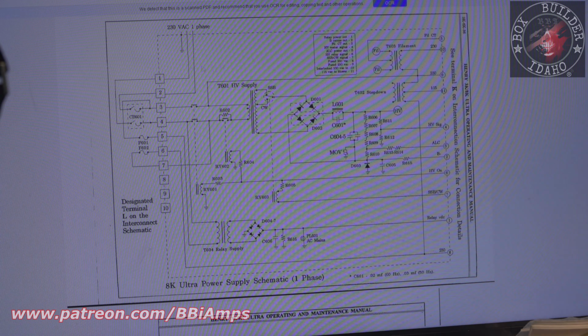Okay, so up here at the top, we have our 230 volt single phase coming in. This is our common case ground. This is one leg, and this is the second leg of the 220 coming in. It comes in, goes through our breaker, like we discussed, and it comes out of our distribution bus, and goes up to these contactors. One leg continues through and goes over, and this is our high voltage supply right here. All of this.